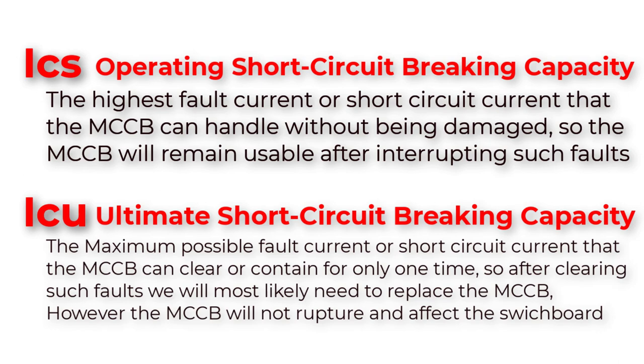The ultimate short circuit breaking capacity (ICU) is the maximum possible fault current that the molded-case circuit breaker can clear or contain, but only one time. After clearing such faults, we will most likely need to replace the MCCB. However, the MCCB will not rupture and will not affect the switchboard. Any fault current above ICU will cause a huge problem because the MCCB will be unable to trap or contain such faults.